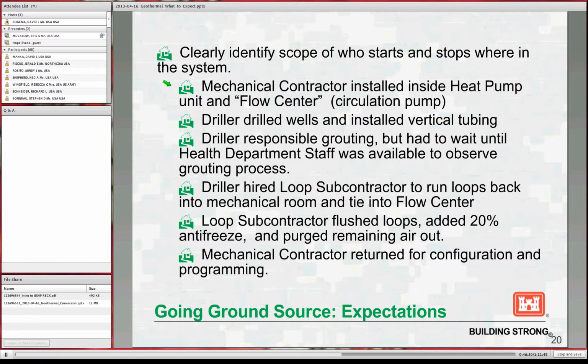Since this was a replacement of an existing system, we did it over the winter so I could use the resistance heat backup. Once the mechanical contractor was able to get the inside system hooked up, we were able to use it with the resistance heat while the loop was still being assembled. In any retrofit installation, you need to figure out what you're going to do without air conditioning or heat while they take the old machine out and before the new one is up and running.